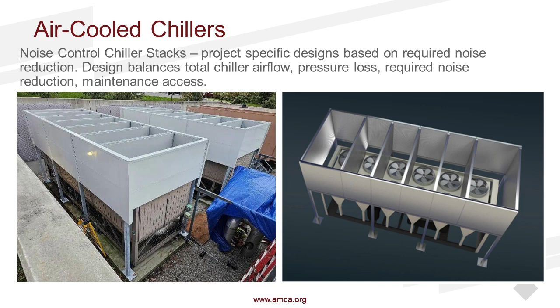What's nice here is it actually helps control recirculation because you're extending that up more. The pressure drop is basically nil other than the perforated inner shell and friction loss. Now, you see here, you say, well, what if one of these fans blows? How do I get in there? Think of this. These have options for each of these bays. You can have an access port, a hinged access port, enough to get a person through and hand a fan through. That's really nice. But remember, a lot of times this is done via retrofit, unplanned monies. People don't want to spend for the added doors and hatches. So they say, we'll just get a hoist and pull them up and over if there's a problem.